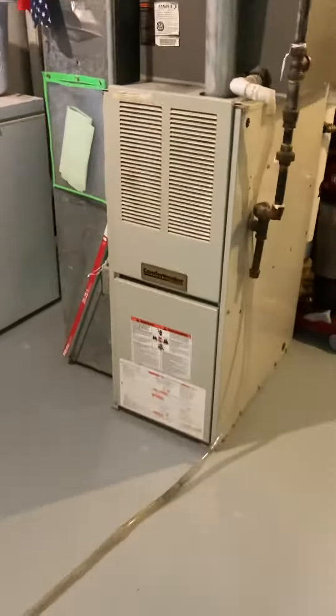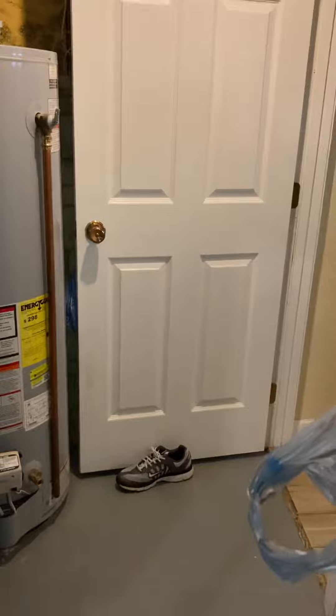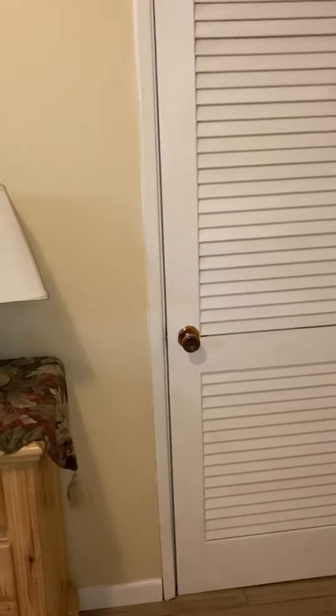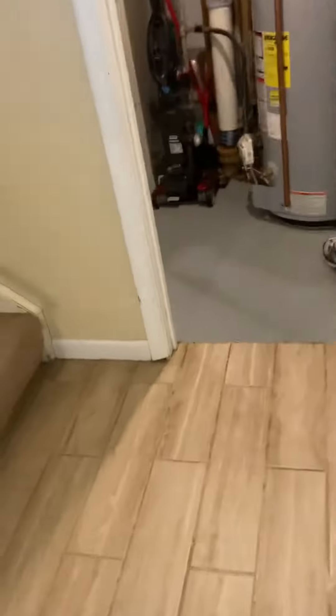One thing is this door here needs to be a louvered door. I mentioned that to the owner and there's actually a louvered door on a closet — it could be used. The hinges need to be changed, but that's it as far as access goes.